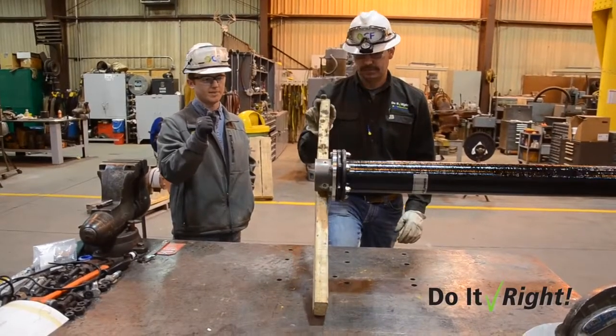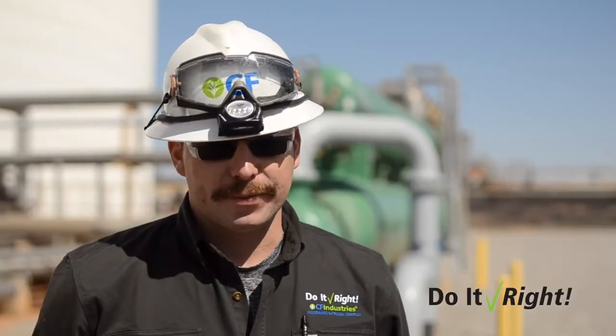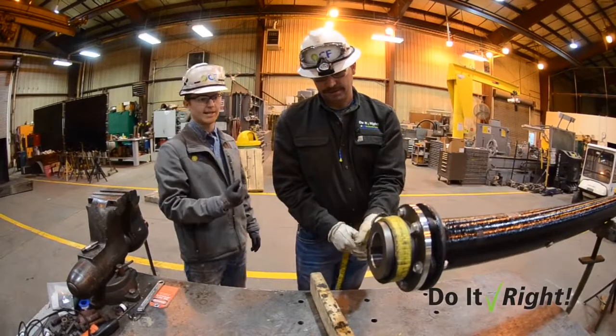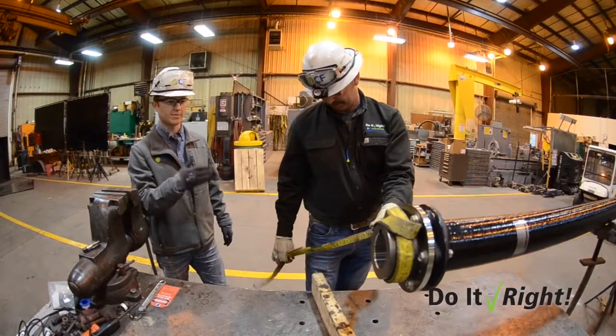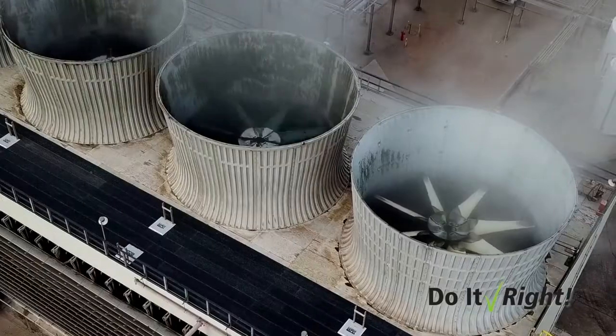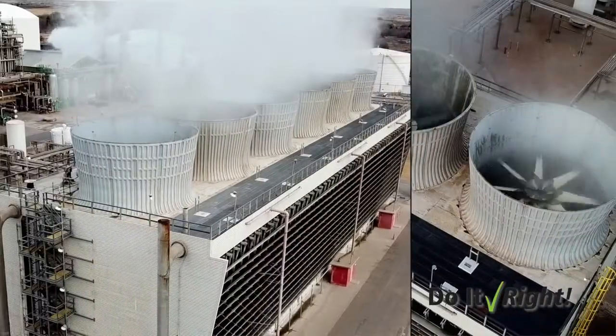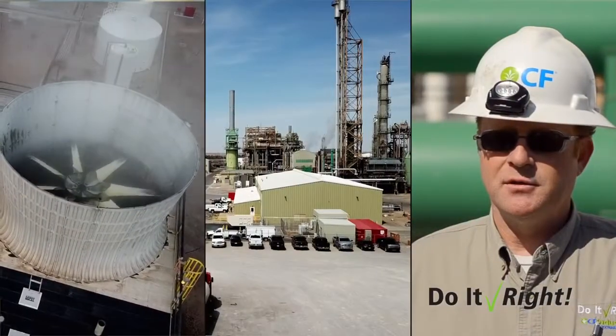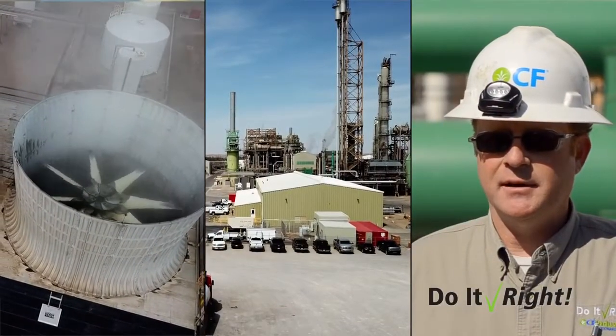We did our normal using a board to stop it. The way we used to stop the fan was we would take a 2x4 and press up against the drive line until it stopped. At that point, we put a strap on the shaft so we could secure it to perform our work, and then we would have to tie it off to keep it from spinning again. It was the industry standard and the only option we had at that time.